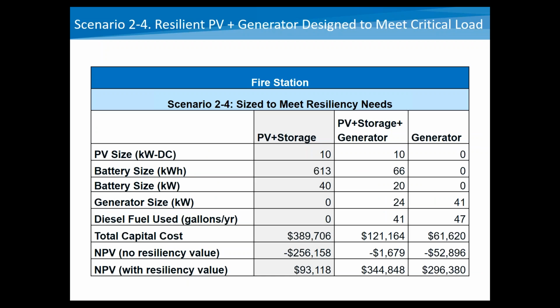This next slide looks at scenarios 2 to 4, which is where we size the systems to meet resiliency needs. In this case, we required the system to sustain a 22-hour outage, and we selected an outage period that we considered a worst-case period, and by that I mean that the solar resource was pretty low and the load was pretty high. And so we felt that if it could sustain that 22-hour period, then it could sustain other 22-hour periods throughout the year.